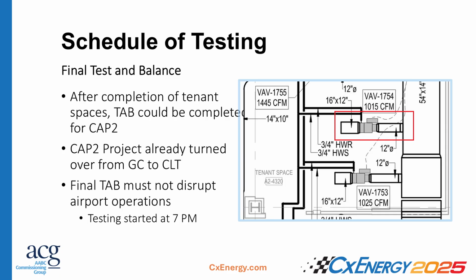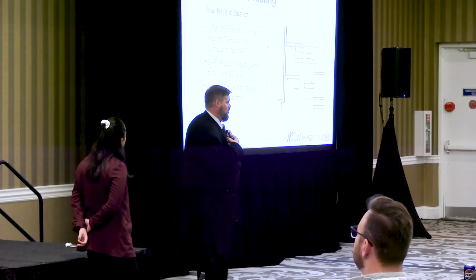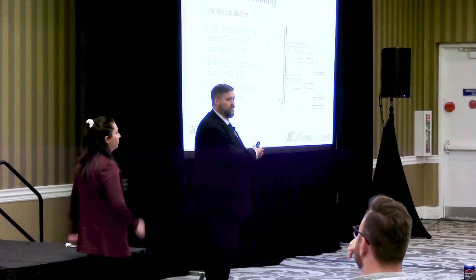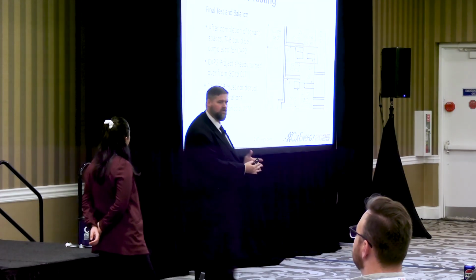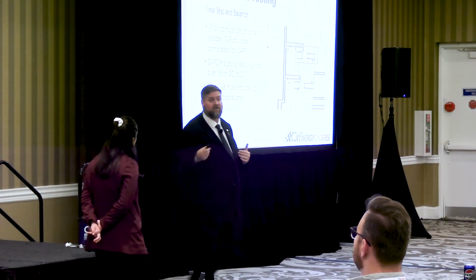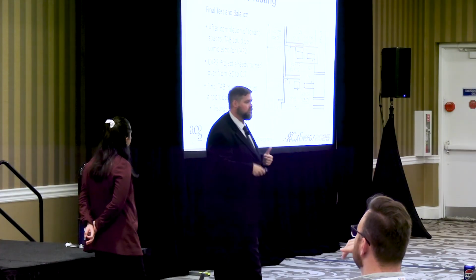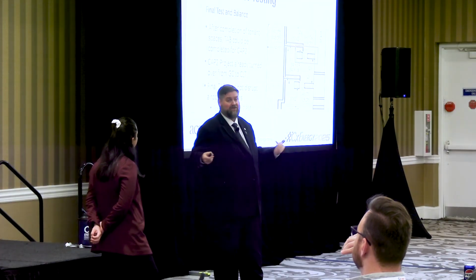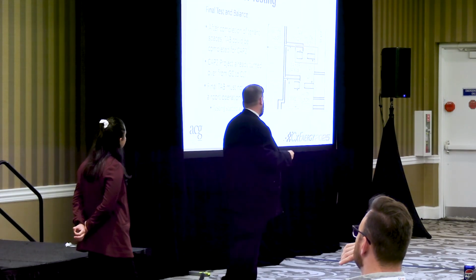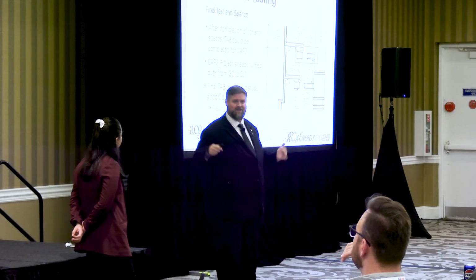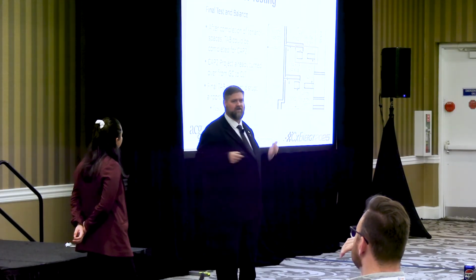The image on the right is what was in our base project, a VAV with hot water reheat capped off for the tenant to pick up. So we looked at our project schedule and said, we can only test so much of this system. We can't test everything; we have to wait for the rest to be done. We did as much as we could on the air handling units to get it through the process, because it was running and working. But we could only test so little on a VAV box where, by the way, the air goes nowhere.